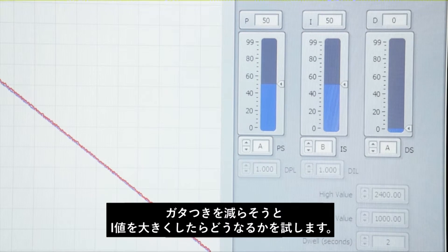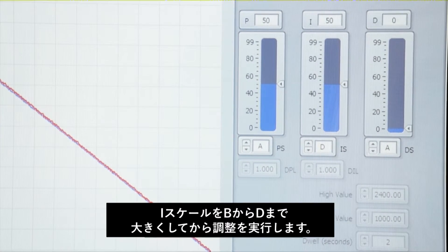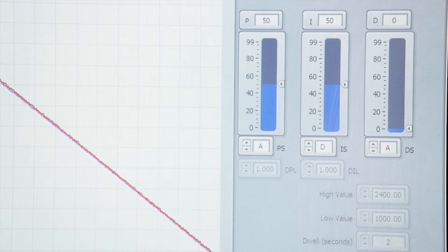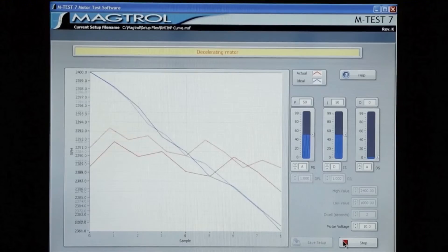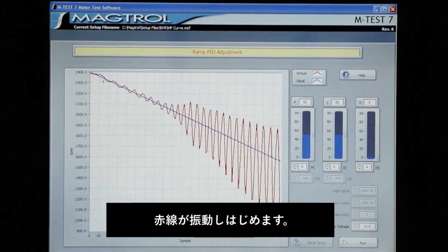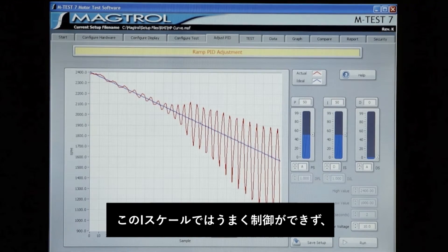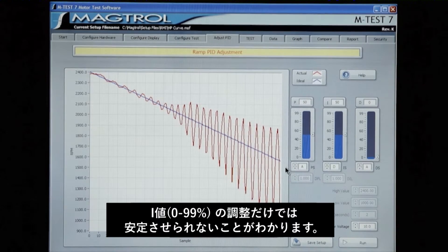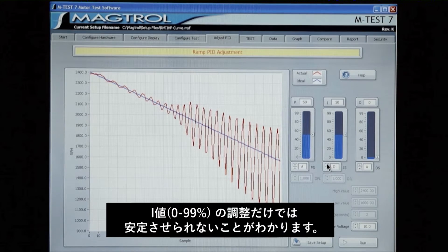To show the effect of going too high on the I term to try to remove this bump, I will increase the scale and run it again. Now you can see immediately that the system has begun to oscillate, and it gets very bad once you get into this range. This is an unusable setting for the tuning adjustment.